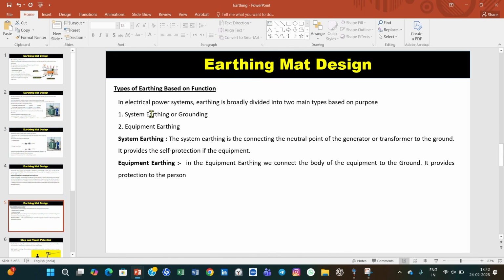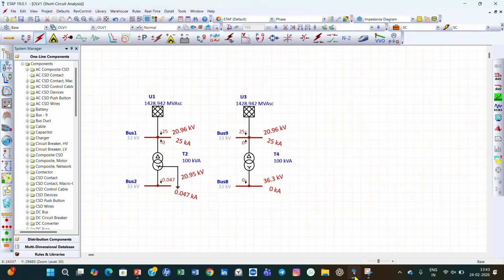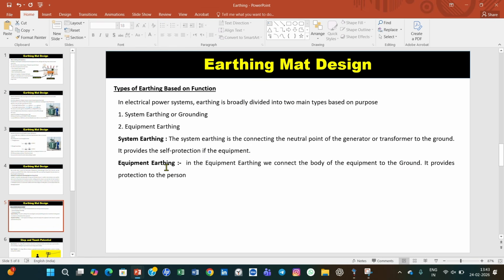Now, types of earthing based on function. In an electrical power system, earthing is broadly divided into two main parts based on purpose: system earthing or grounding, and equipment earthing. System earthing is connecting the neutral of the transformer or a generator to the ground. It provides self protection of the equipment, which I have explained in the ETAP here. And second is equipment earthing, in which we connect the body of the equipment to the ground. It provides protection to the person, which I have already explained to you.